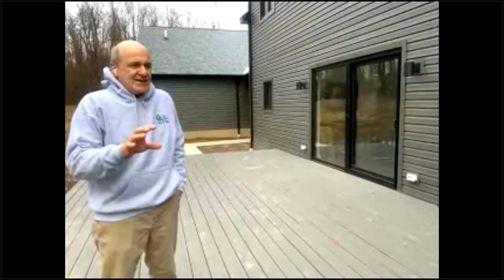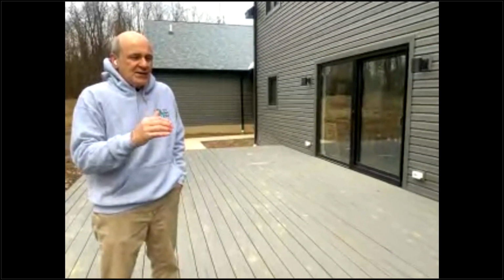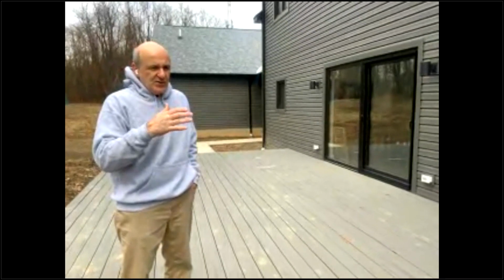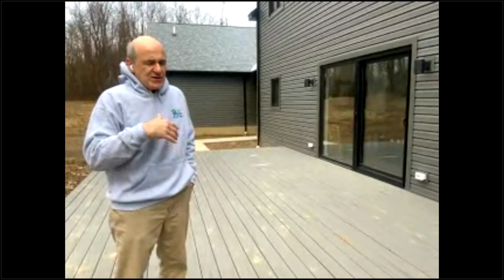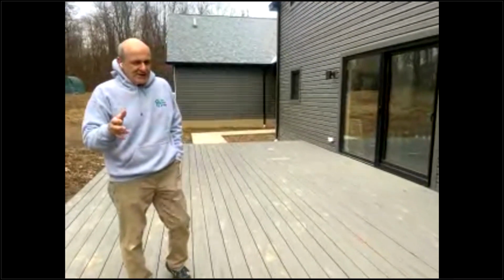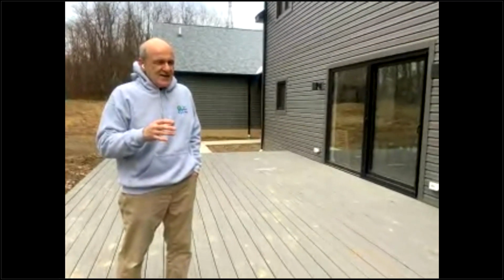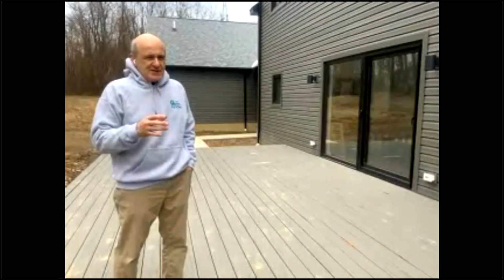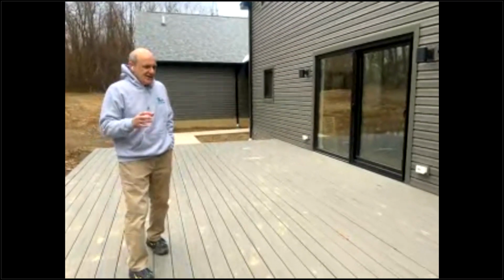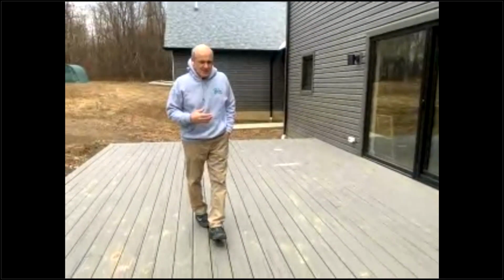We've had to get used to the fact that the heat pump brings in very mildly tempered air, so you can't have really wide swings in the load or any big setbacks or anything like that. So we're learning about all those things. I did take some thermal pictures last night. I don't have them in the slide deck, but I was looking at the different walls and surfaces, like the vaulted ceiling and other areas, and only seeing 2 to 3 degrees Fahrenheit difference between high and low walls, which is what we designed to make this an energy efficient home to take care of the expensive air that we're creating.